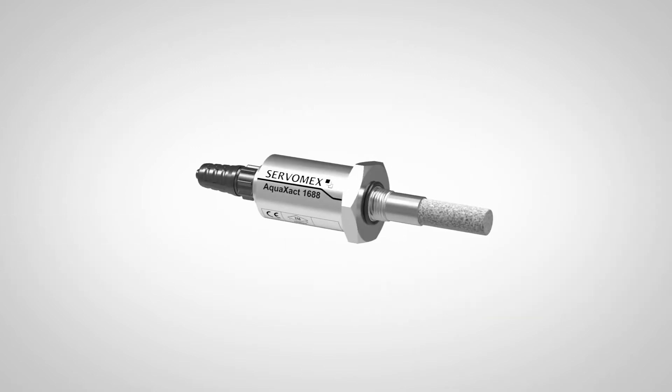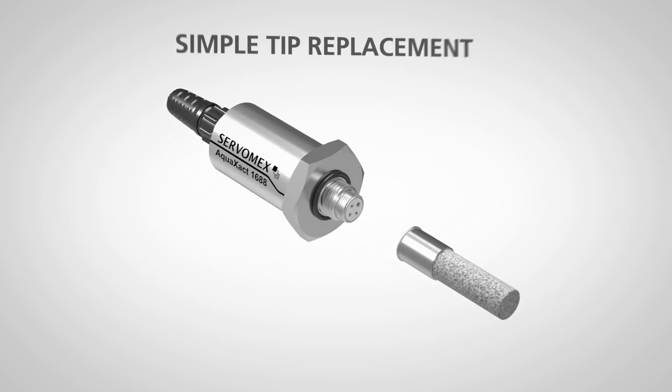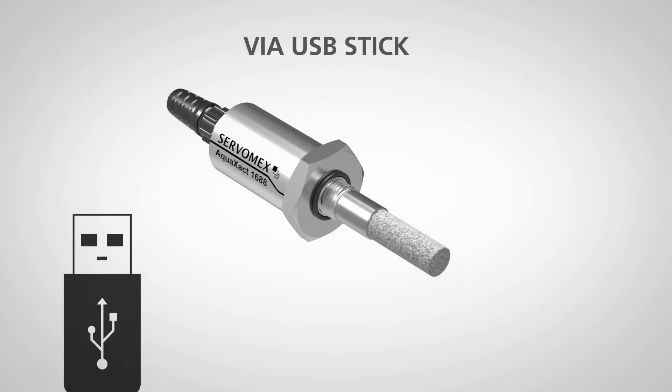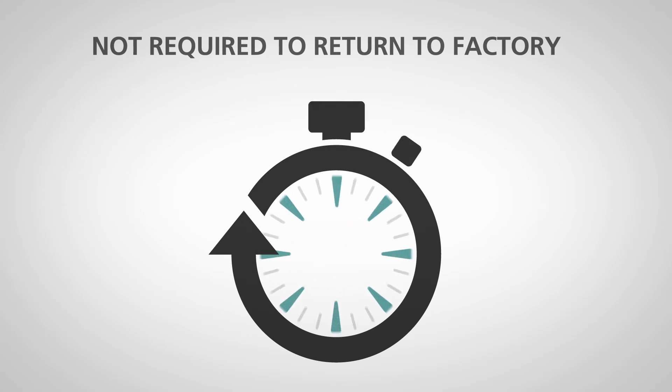It's easy to replace the AquaXact sensor tip in the field without losing measurement quality. Simply upload the calibration file using the USB port on the MonoExact DF310E. There's no need for return-to-factory calibration, which saves you time and money.